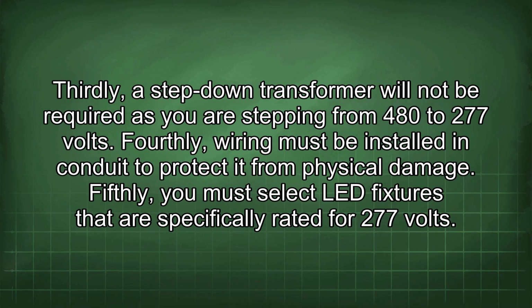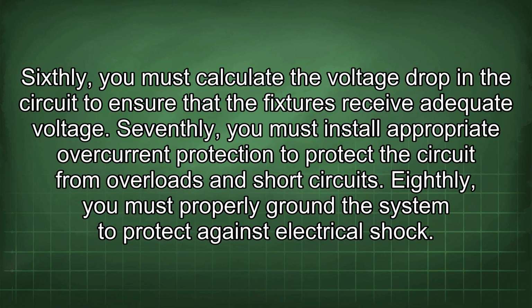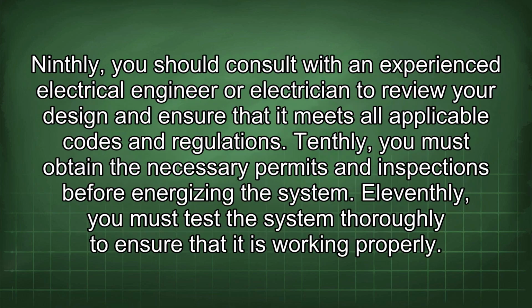Fourthly, wiring must be installed in conduit to protect it from physical damage. Fifthly, you must select LED fixtures that are specifically rated for 277 volts. Sixthly, you must calculate the voltage drop in the circuit to ensure that the fixtures receive adequate voltage. Seventhly, you must install appropriate overcurrent protection to protect the circuit from overloads and short circuits. Eighthly, you must properly ground the system to protect against electrical shock. Ninthly, you should consult with an experienced electrical engineer or electrician to review your design and ensure that it meets all applicable codes and regulations.